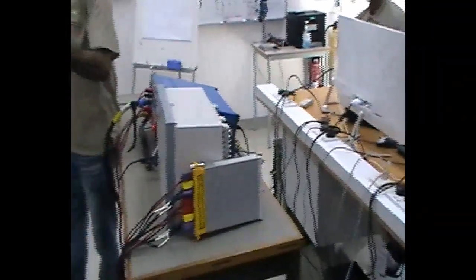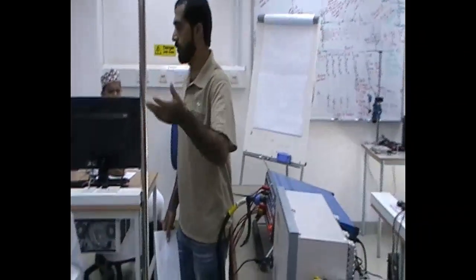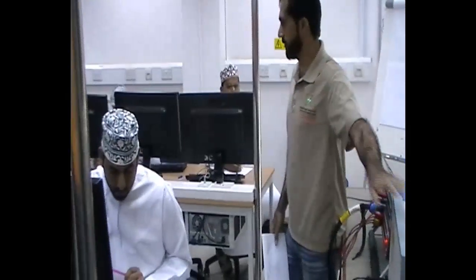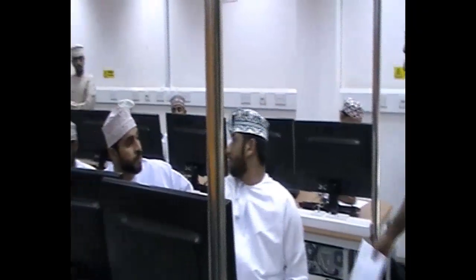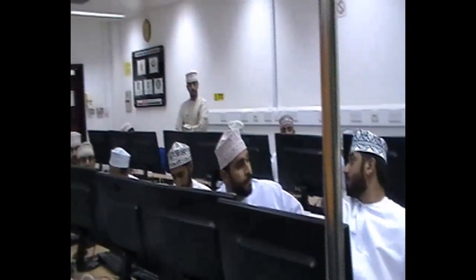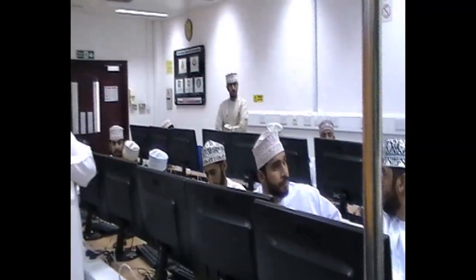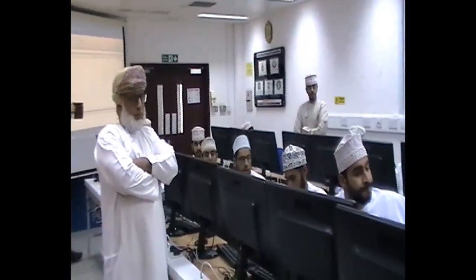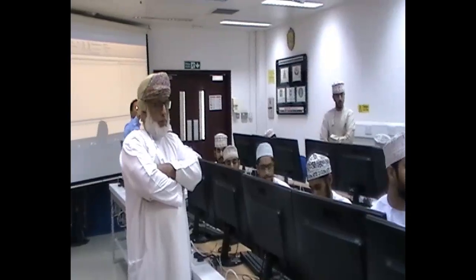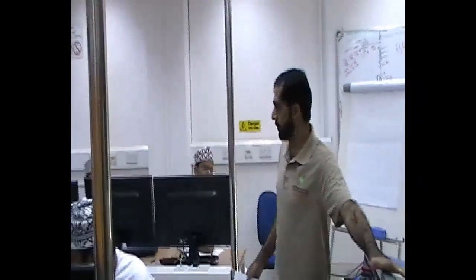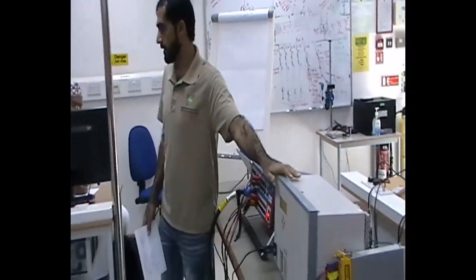We have other functions. These relays are numerical relays and have different functions. One relay contains differential, distance, overcurrent, maybe either voltage or current protection. It's multifunction. We can enable whatever we want, and we'll go through the configuration of the relay. Now, this is a very reliable device. It usually comes with a warranty of about 10 years, so it's almost free of maintenance. But what we need to make sure of is the setting inside the relay.